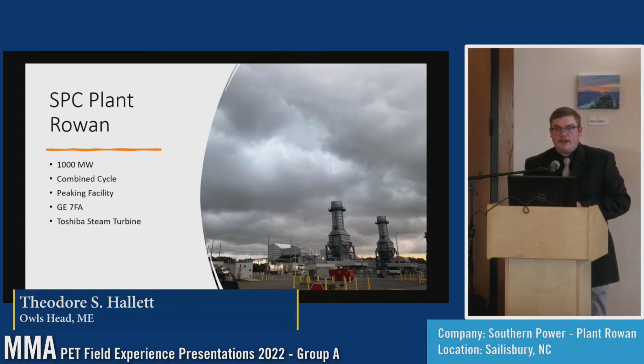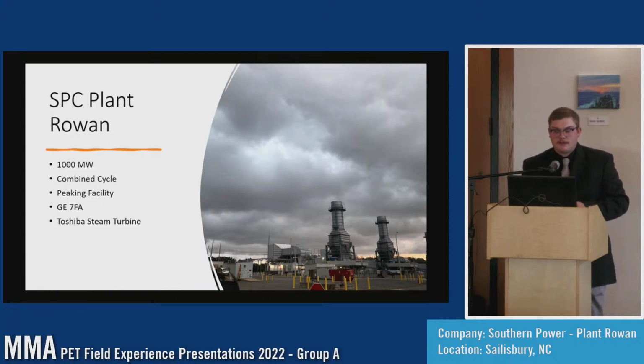So I did my co-op at Southern Power Company Plant Rowan. This is based out of Rowan County in North Carolina. It is a 1,000 megawatt plant, and it uses both combined cycle and peaking. Phase 1 is the peaking side, and that runs 3 GE7FA turbines. Those run on liquid fuel and natural gas, and the combined cycle uses 2 GE7FA gas turbines, and only one of those is liquid fuel capable. The other is just natural gas, and 1 Toshiba steam turbine.